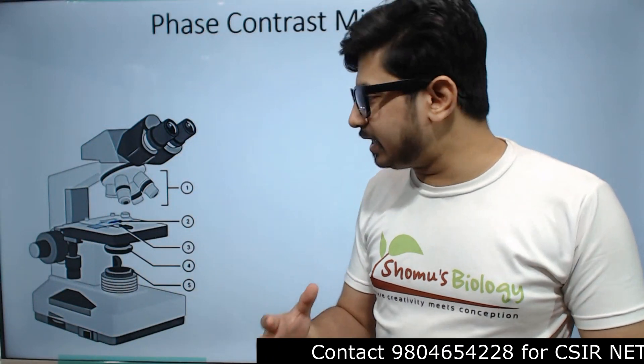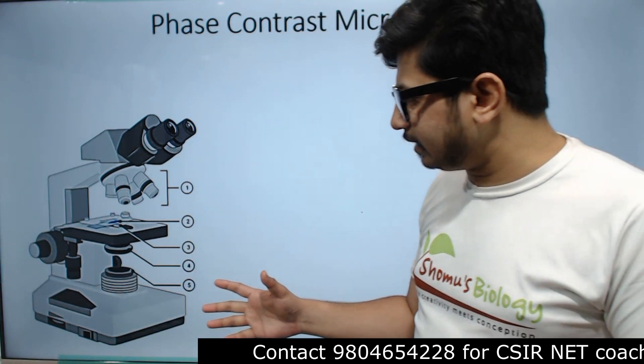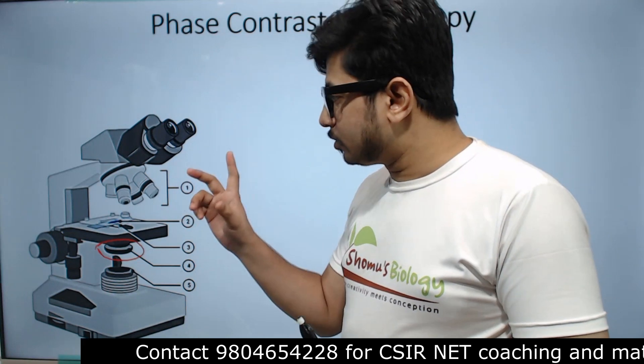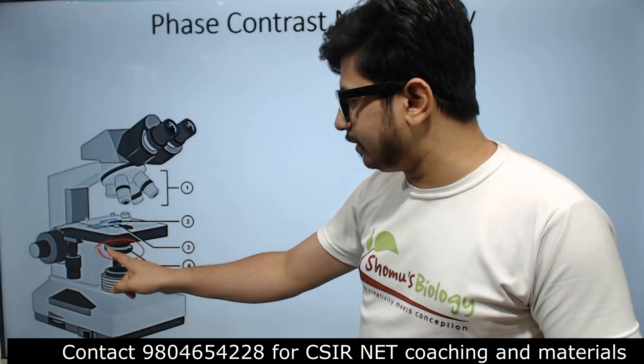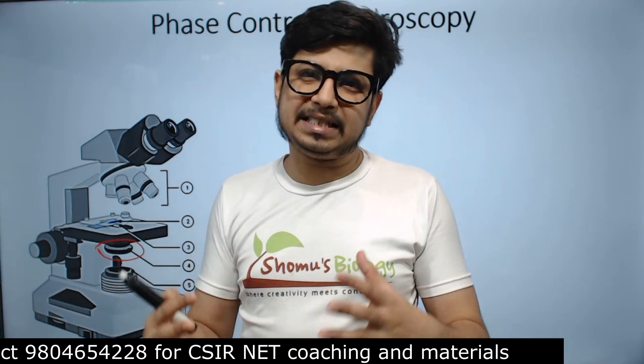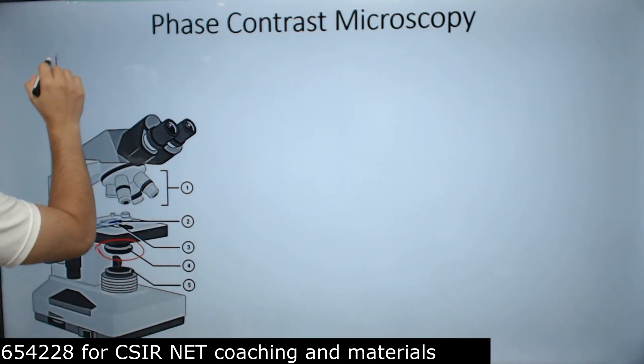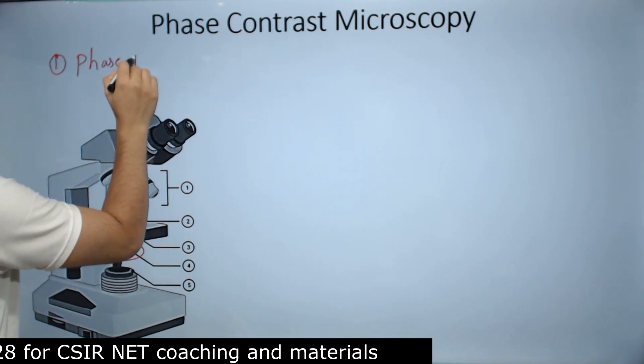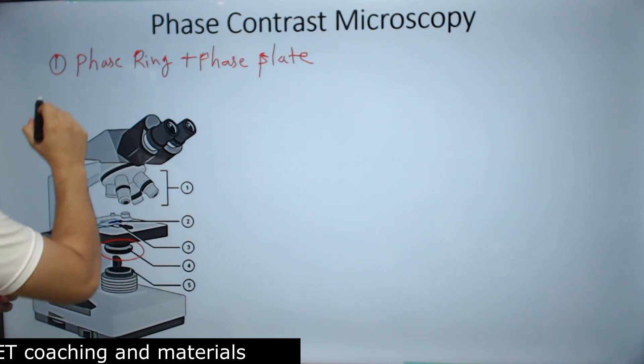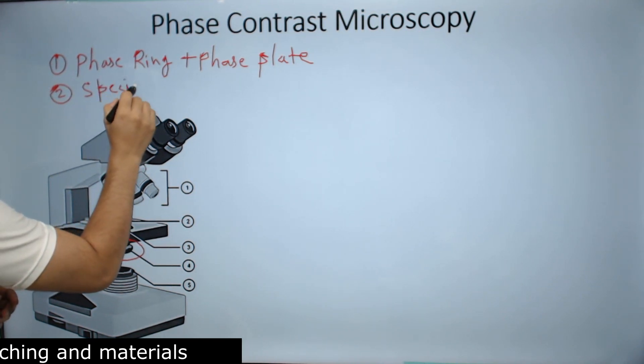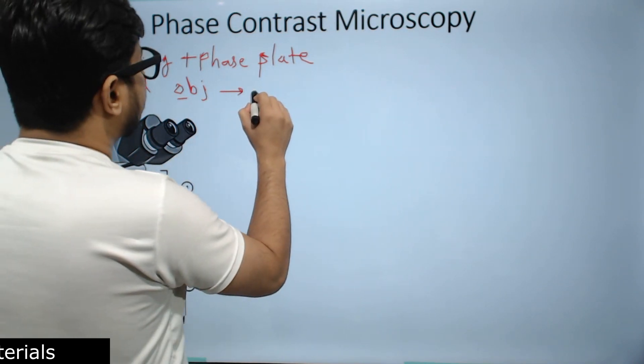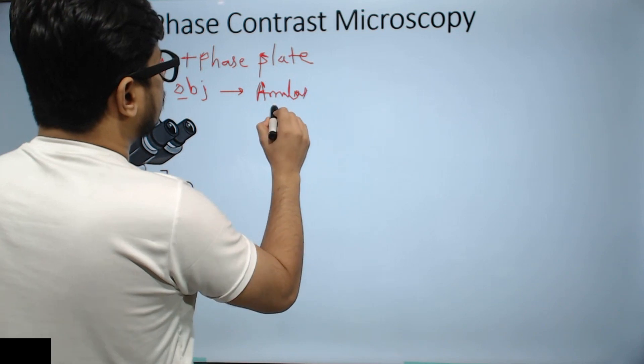Before going further, I want you to know how it looks. In phase contrast microscopy, one thing is unique — the phase plate, which is not drawn in this particular picture. So everything will be similar except the phase plate, which is the major component. Without the phase ring, a phase contrast microscope is useless. The extra components are the phase ring and phase plate, along with specially modified objective lenses known as phase contrast objective lenses, because they contain what is known as a phase annulus.